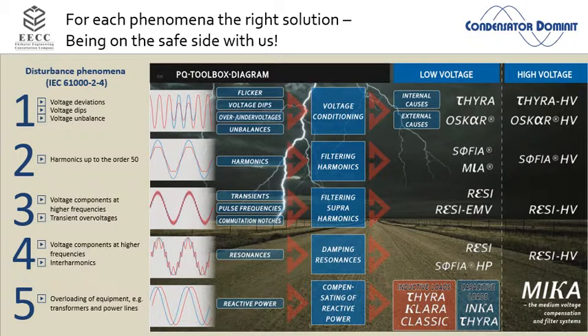That's also power quality. Does anybody have a feeling? Now I'm really unfair, I know, but I like it. What is the typical inductivity, stray inductance of a transformer, 13 kilovolts or 10 kilovolt down to 400 volt, 1 MVA? It's unfair, I know. I calculated it myself. It's about 30 microhenry. Okay? And a 1 MVA transformer has roughly 30 microhenry stray inductance.